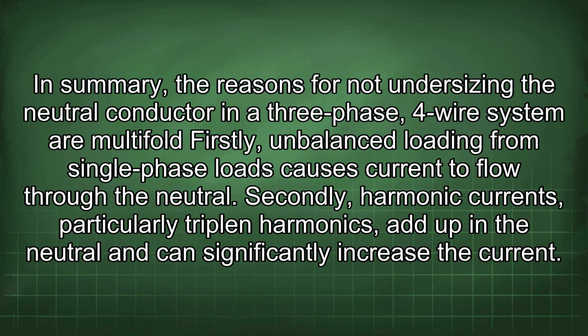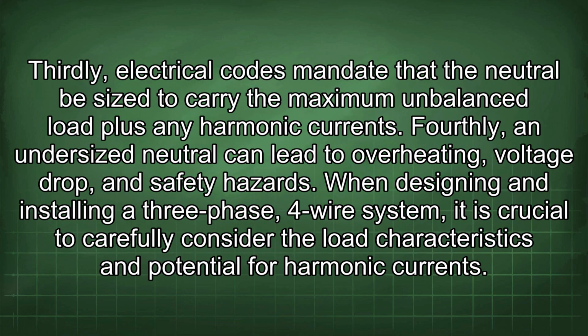In summary, the reasons for not undersizing the neutral conductor in a three-phase, four-wire system are multifold. Firstly, unbalanced loading from single-phase loads causes current to flow through the neutral. Secondly, harmonic currents, particularly triplen harmonics, add up in the neutral and can significantly increase the current. Thirdly, electrical codes mandate that the neutral be sized to carry the maximum unbalanced load plus any harmonic currents.